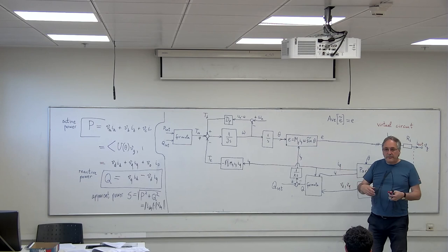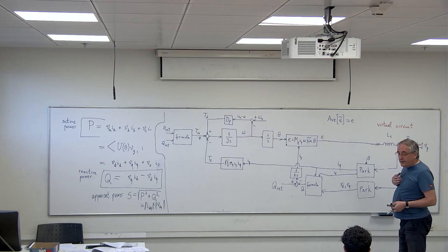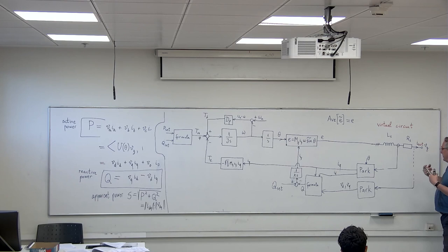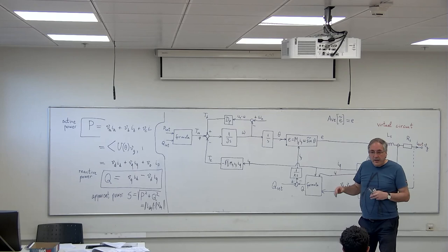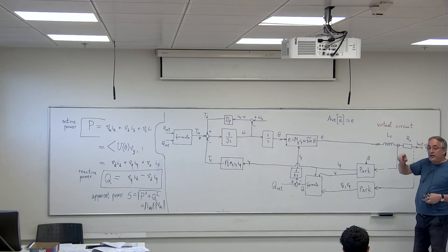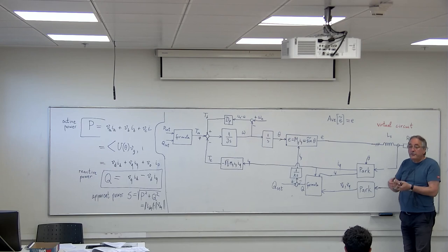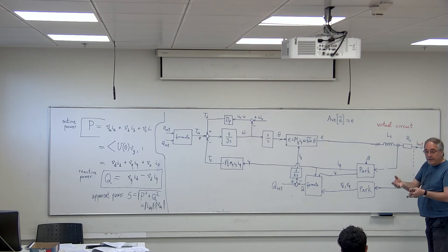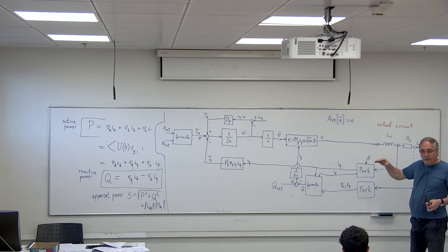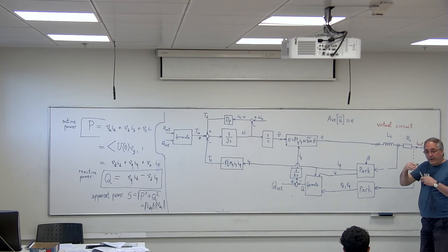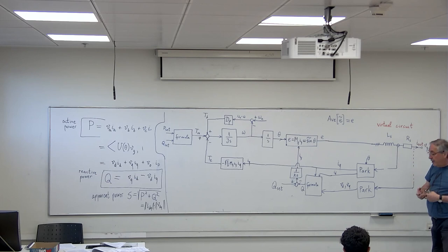So in order to avoid that, I take these virtual currents in Park transformed variables, in D and Q, which are not changing fast. And these Park transformed virtual currents, virtual ID and virtual IQ, I can limit by saturation blocks. After they pass these saturation blocks, in order to avoid overcurrents, the clipped ID and IQ, clipped in the DQ domain, not in the time domain, not in the usual sinusoidal domain, become reference currents for my current sources, which generate the true grid currents.